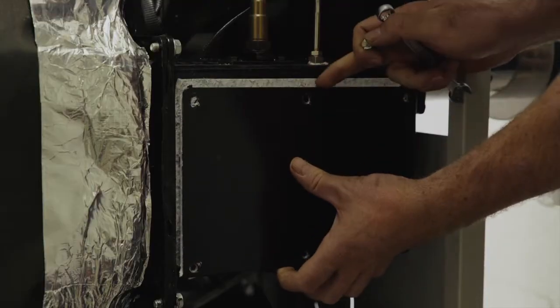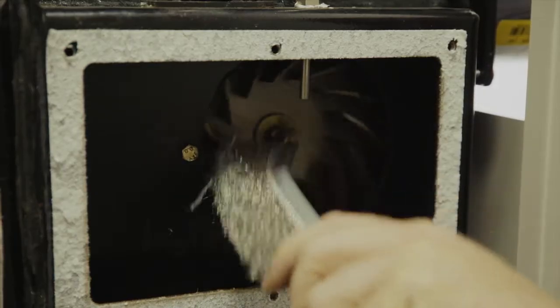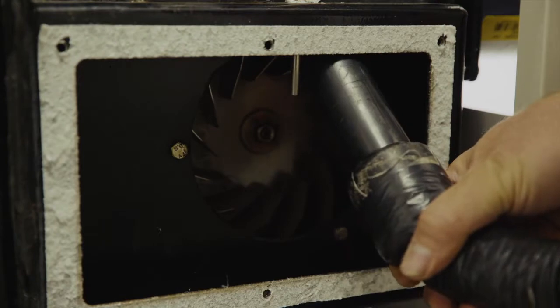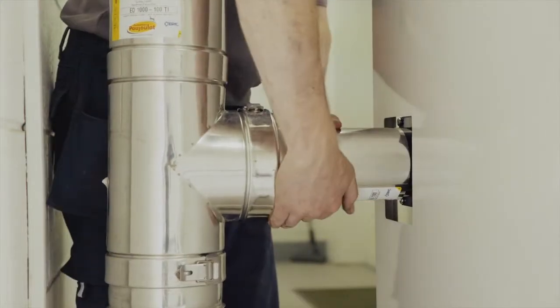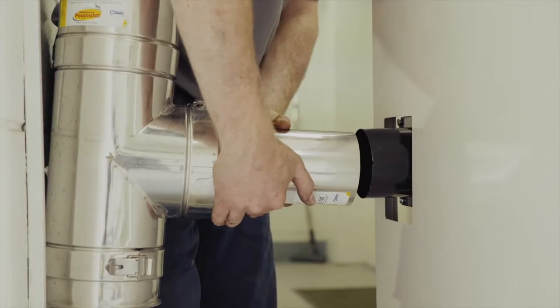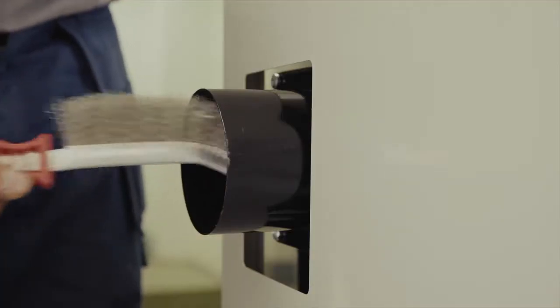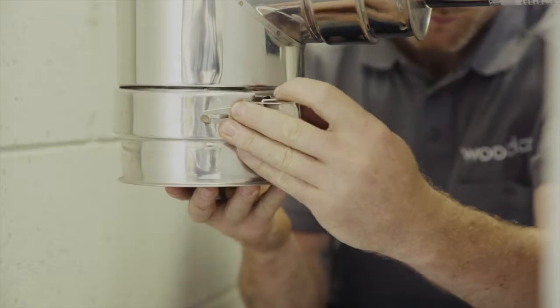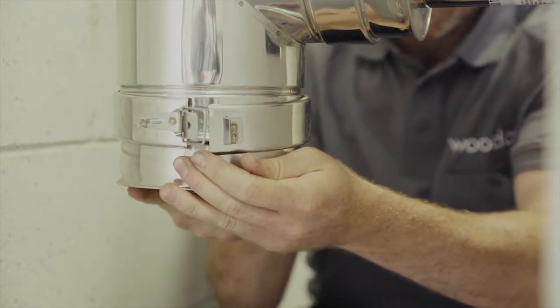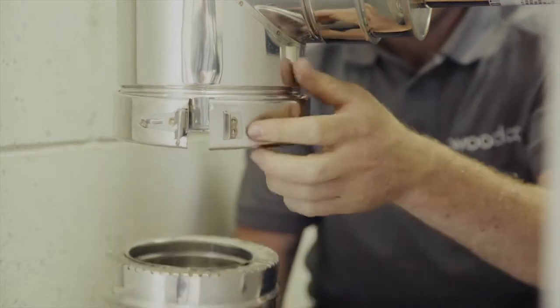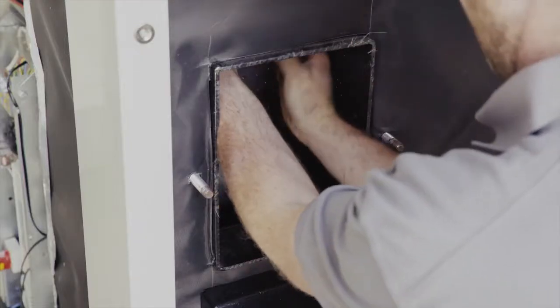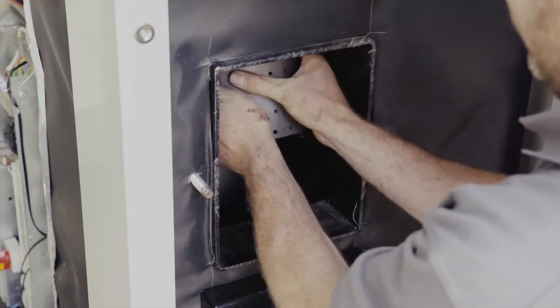Remove exhaust access plate and clean flue gas passageways to the flue outlet. Remove and clean the flue gas thermocouple. Completely clean the flue through the inspection door and remove the flue.